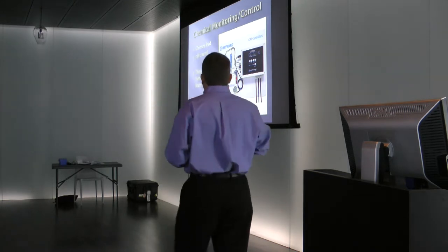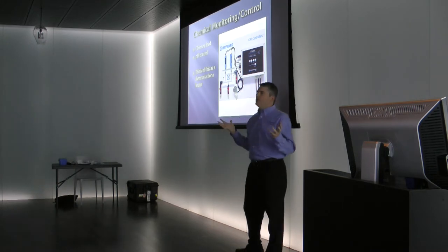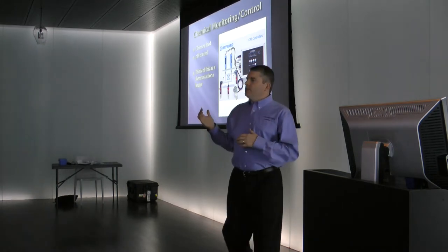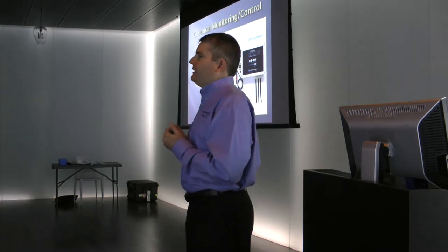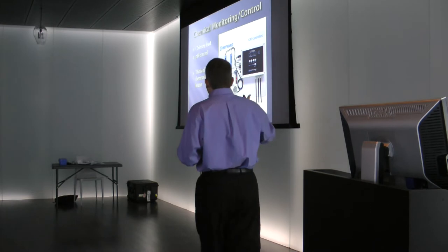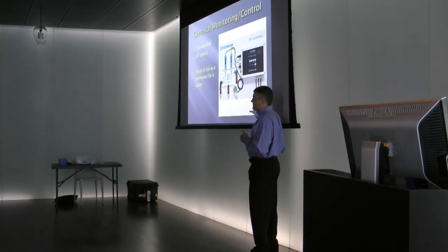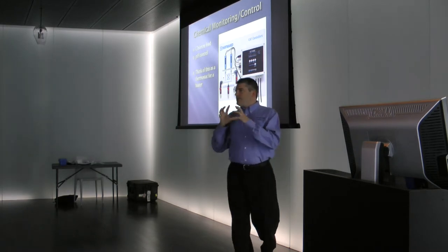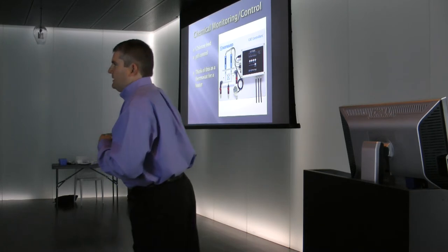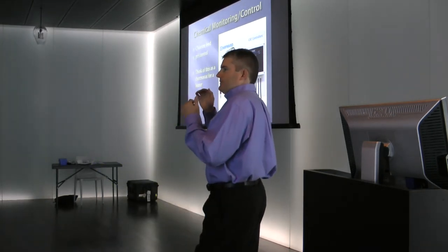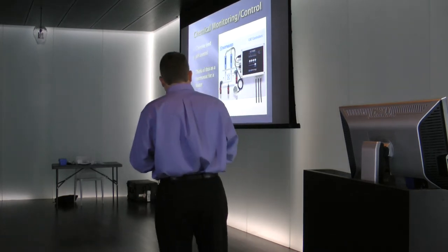You have a set point in here, measured in millivolts. So you might set this to, let's say, 700 millivolts. And if the body of water drops below that set point, this system powers up a pump. One of these lines is powered in, and one goes to a little medical-type pump, a peristaltic pump, and it just injects chlorine until you get back to 700. Just like a thermostat setting the temperature in the room.